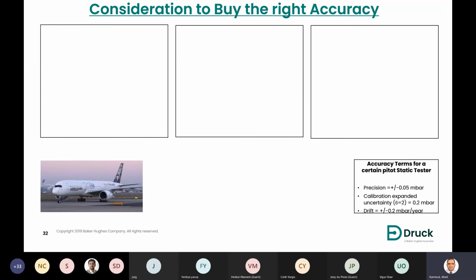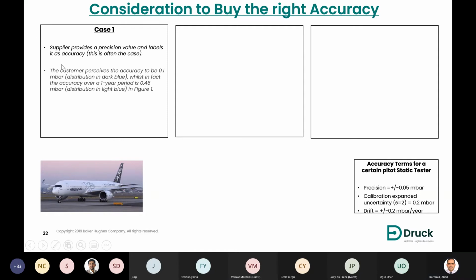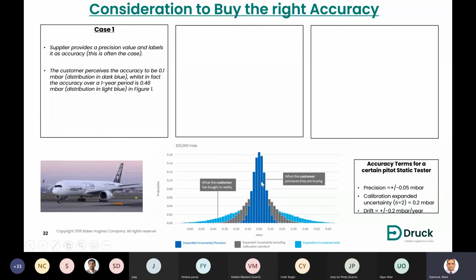We will see now three ways to write these specifications on the datasheet. Case number one: a lot of people do that. It's often that people provide the precision value and label it as accuracy. So the customer, if you require 0.1 millibar for this airplane, will see that this 0.05 millibar is twice better, so it's good. This is what you expect, the one in dark blue. While in fact, the accuracy over 1 year is 0.46 millibar, which is the light blue.